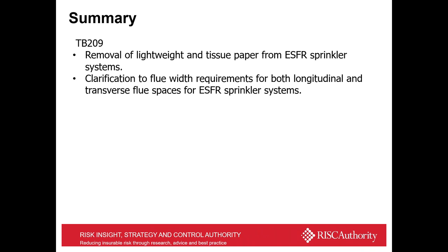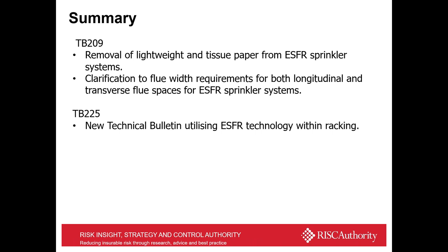Removal of TB209, which is ESFR. So we've removed lightweight tissue paper from ESFR systems, and we've clarified the flue width requirements for both longitudinal and transverse flues, because there was a slight bit of added complication with regards to whether any obstructions were allowed within these clear air flues. TB225, well, it's pretty straightforward. It's a brand new technical bulletin on utilizing ESFR sprinklers within racking.